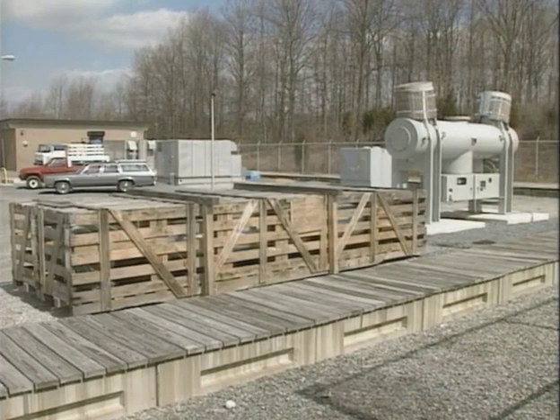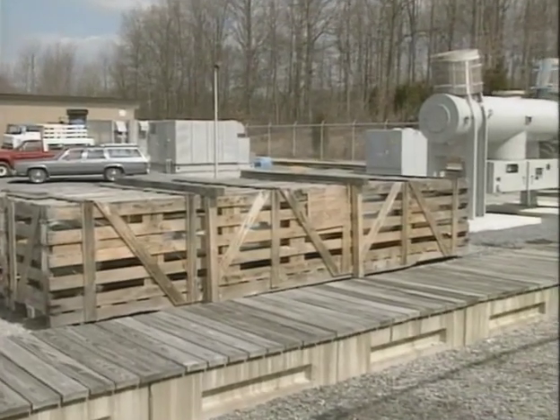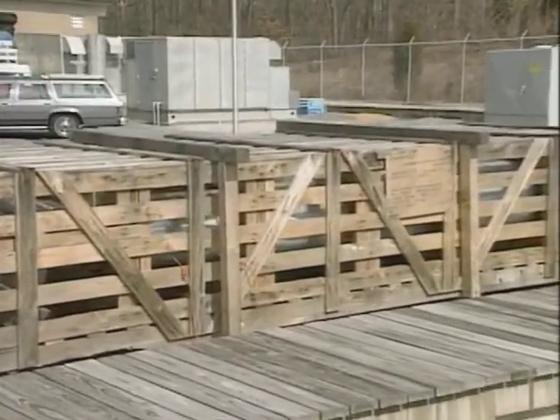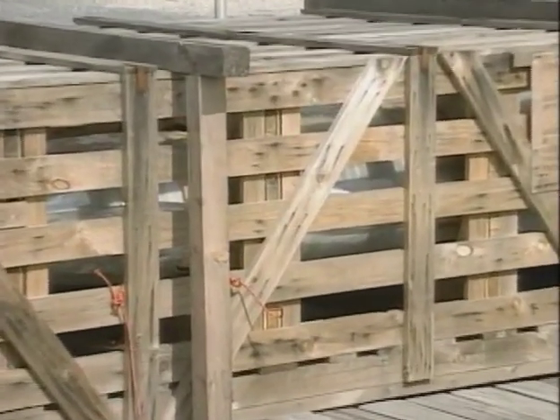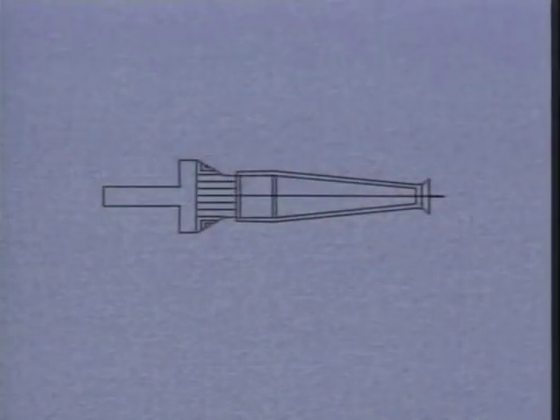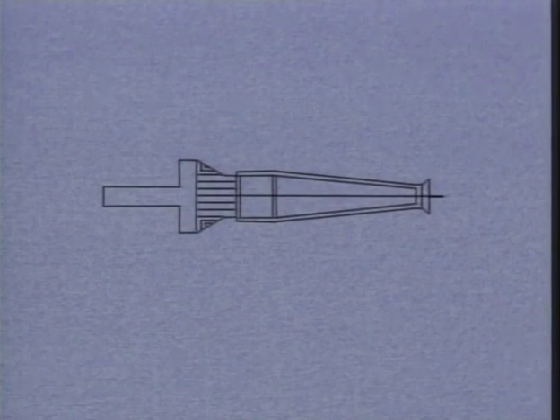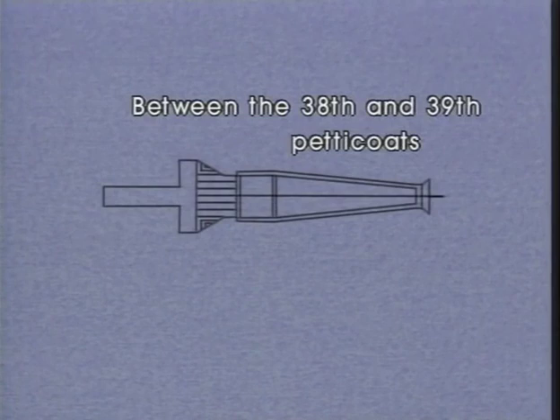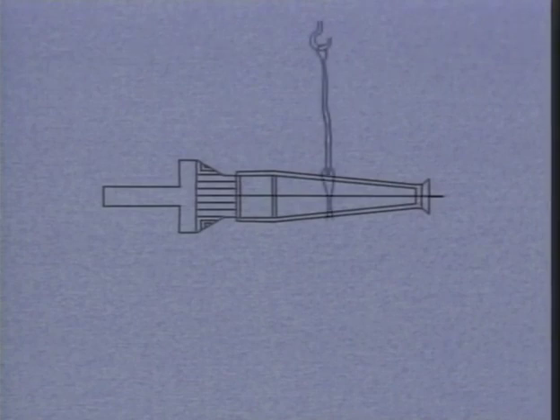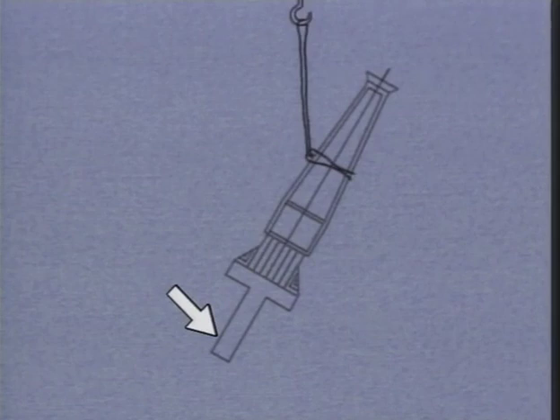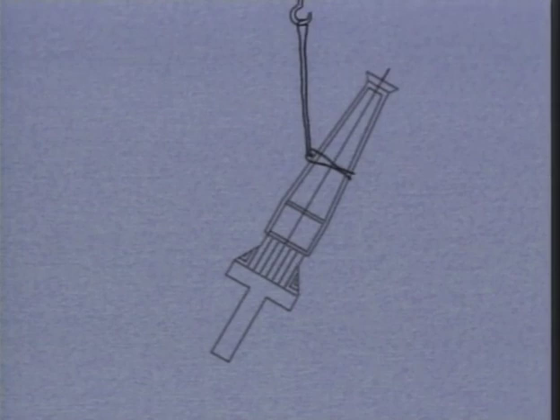The bushings for this gas breaker are installed using a completely different procedure from the one followed for the oil-filled bushings. The bushings for this breaker do not contain oil, and they are relatively light compared to the oil-filled bushings that we just looked at for an oil breaker. The manufacturer of this breaker and its bushings recommends that a nylon sling be placed around the bushing between the 38th and 39th petticoats, counting down from the top of the bushing. Because the bushing is light, lifting the bushing in this manner shouldn't damage it. A shipping cover protects the bottom of the bushing until it's lifted clear of the ground. Proper placement of the nylon sling will give the bushing the proper tilt needed to install it in the breaker.